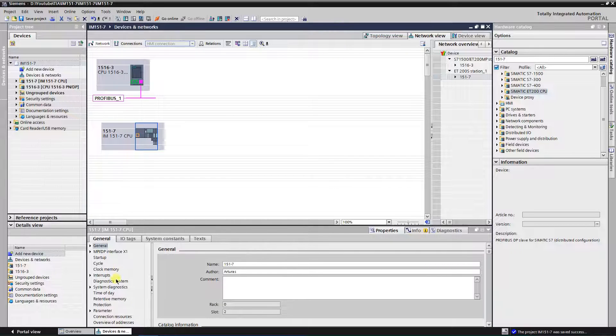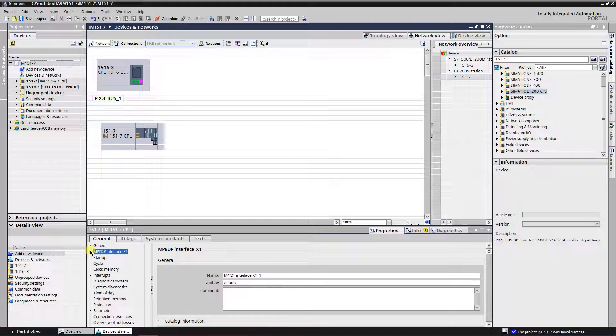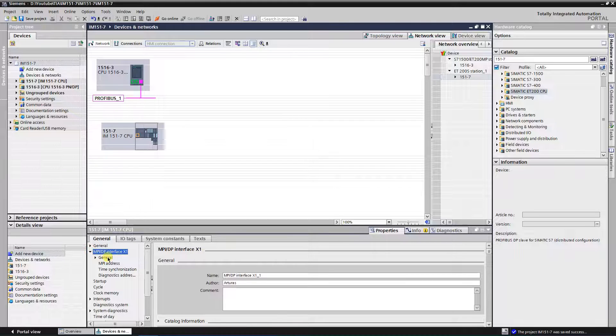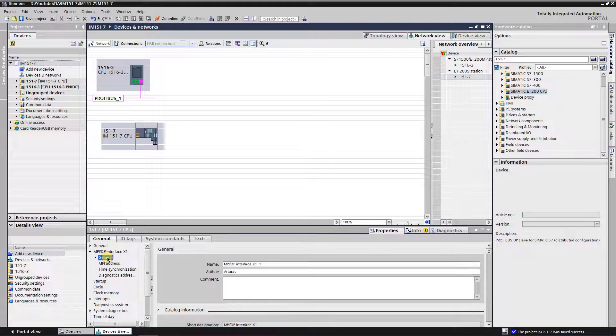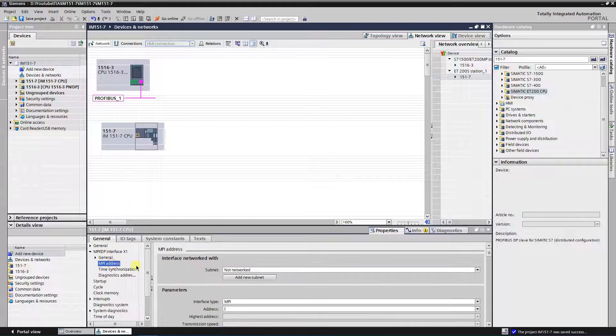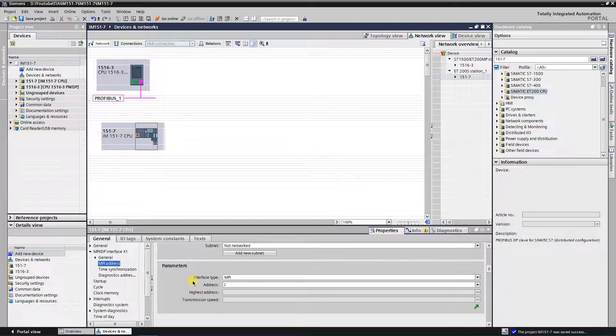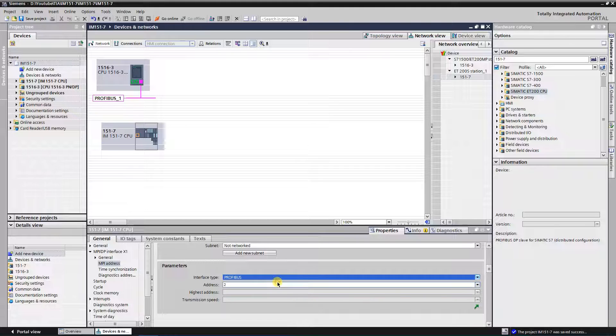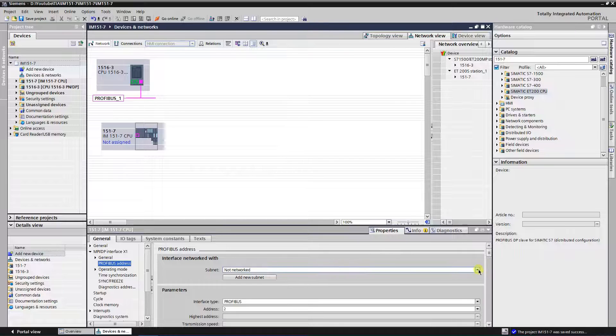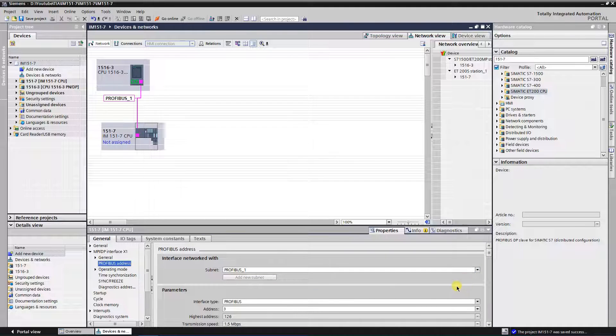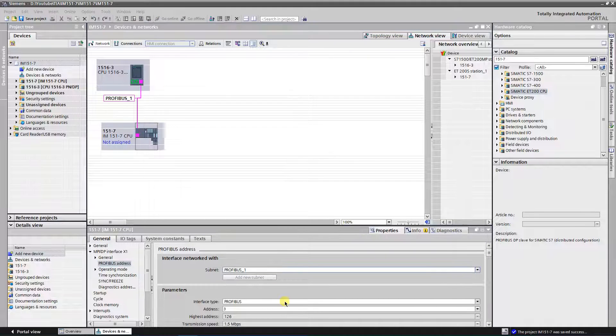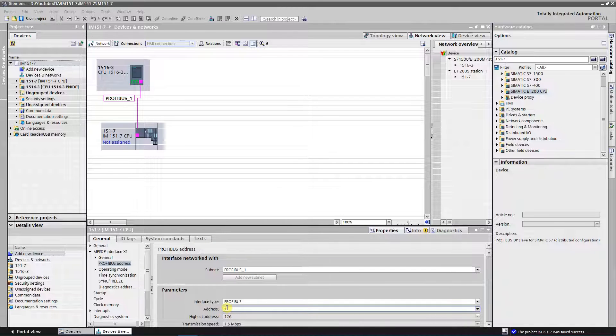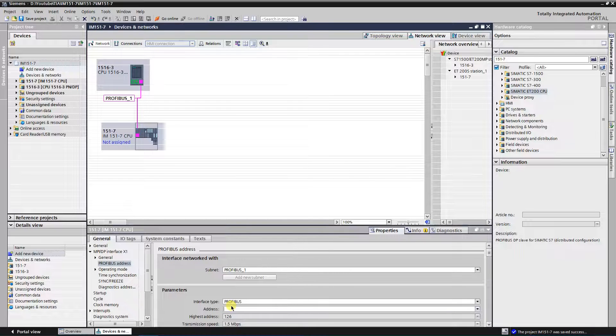Select your IM151-7 CPU, find the MPI/DP interface properties under the General tab and expand it. Select MPI address, and in the parameters you can change interface type from MPI to PROFIBUS. Select your DP master system from the drop down menu in the interface subnet. Your IM151-7 will become a slave on it. Change the number of PROFIBUS address to the one that is suitable for you.